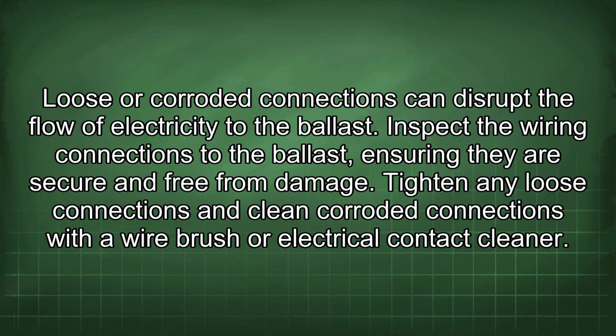Loose or corroded connections can disrupt the flow of electricity to the ballast. Inspect the wiring connections to the ballast, ensuring they are secure and free from damage. Tighten any loose connections and clean corroded connections with a wire brush or electrical contact cleaner.